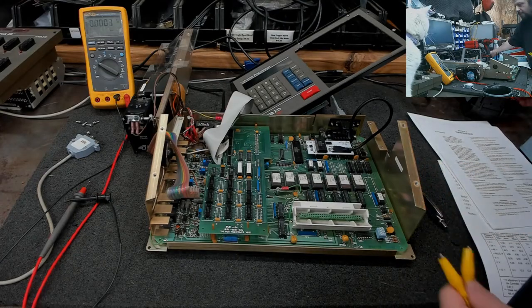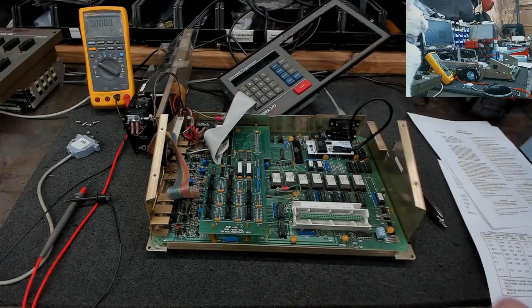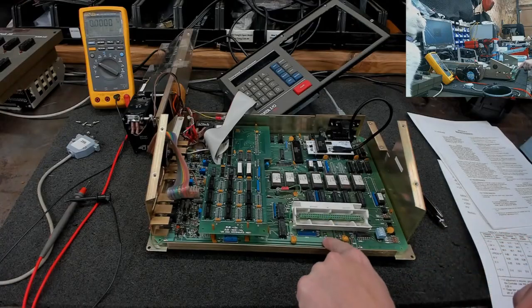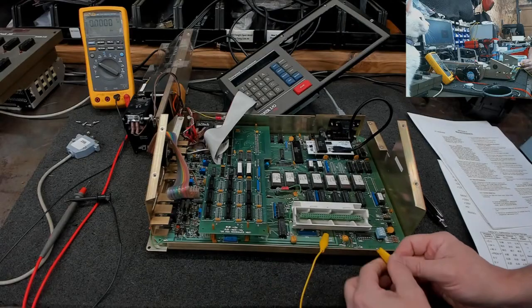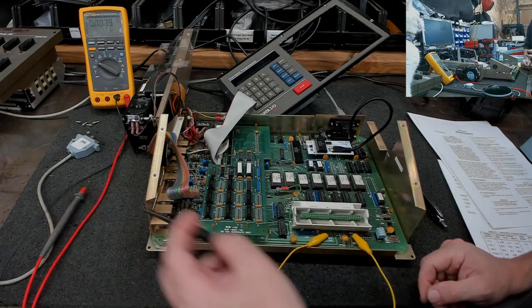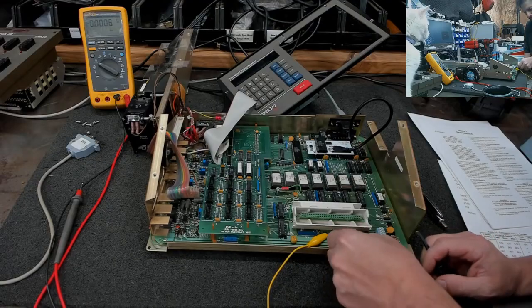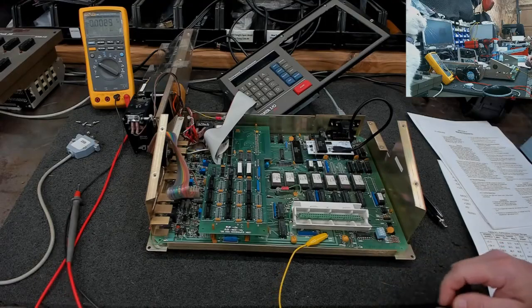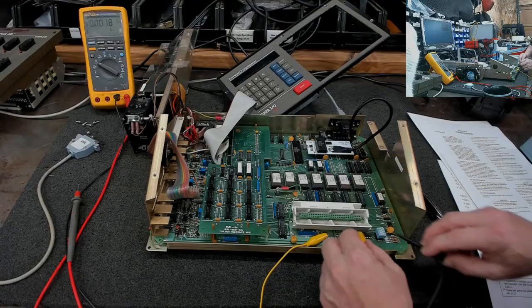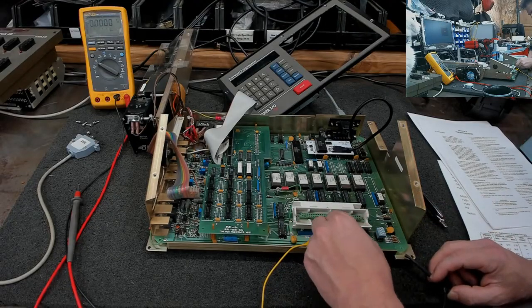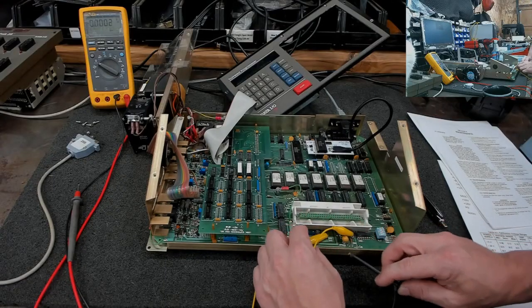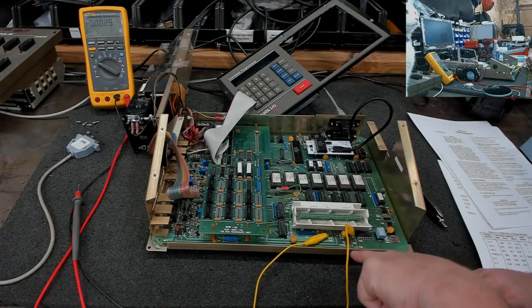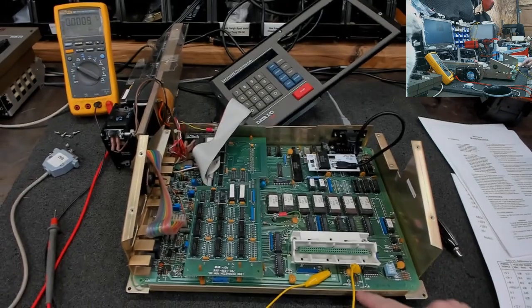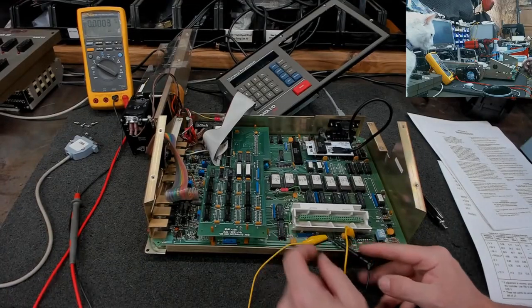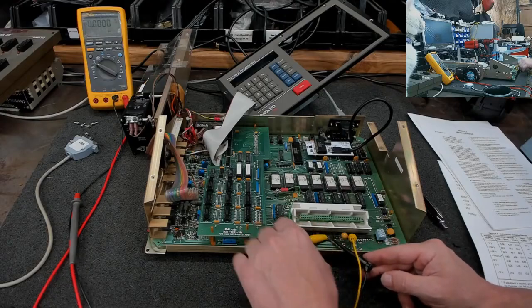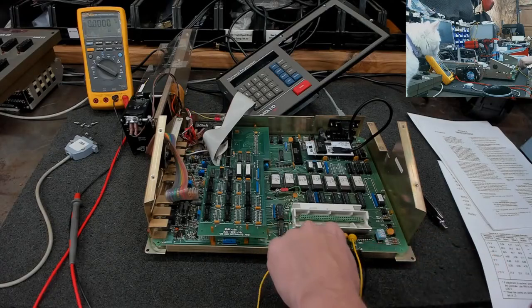So before you power this up, you want to go from test point 2, which is ground, to test point 3 with a jumper. That's what it says in the instruction manual. And then you want to take your ground and you don't want to cover up this 10 volt right there. Believe it or not, it says 10 volts right there. So go like that. And you don't want to cover up right here either. It says plus PROG. That's one of the test points. And you want test point 1 right there too. So kind of a pain, because your test point 1 is your 5 volts.